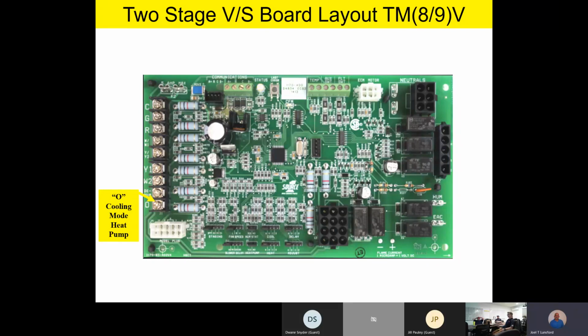And it doesn't hurt anything. It certainly doesn't burn anything up or anything like that. But again, we'll talk about this jumper more when we start getting into jumpers. Just make a mental note that if you have it on a heat pump, you have to have it in the heat pump position. But if you don't have it on a heat pump, make double sure when you commission this board that it's on the AC jumper.